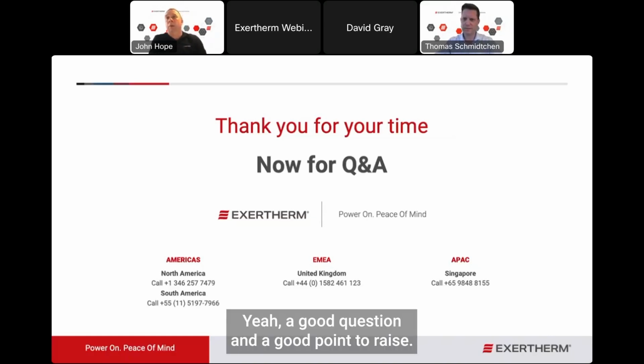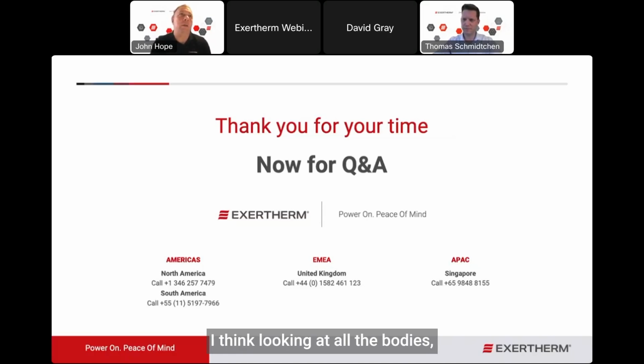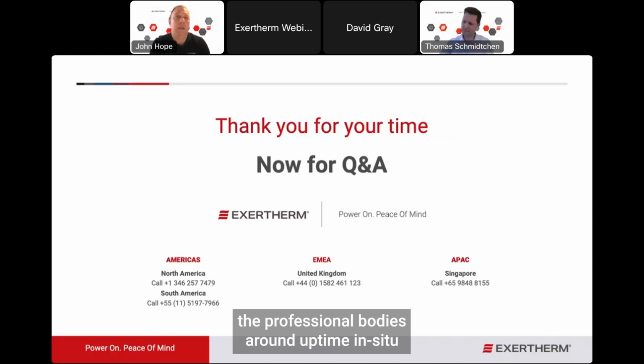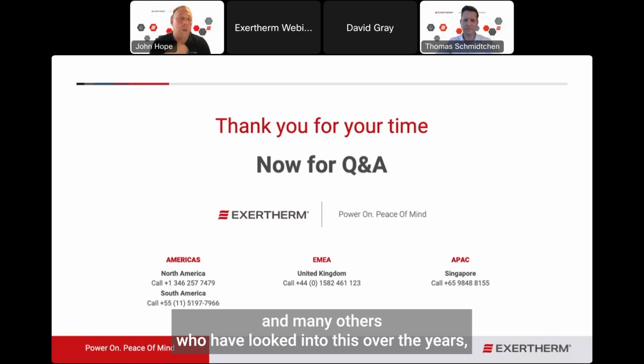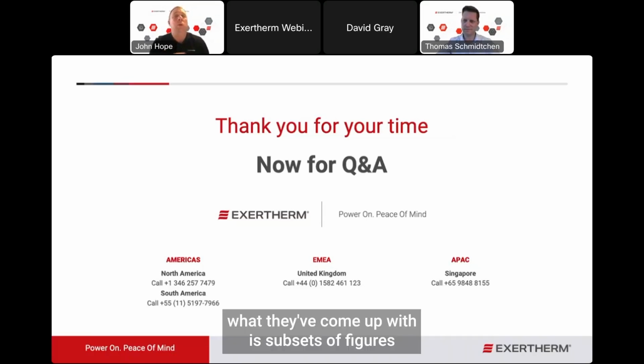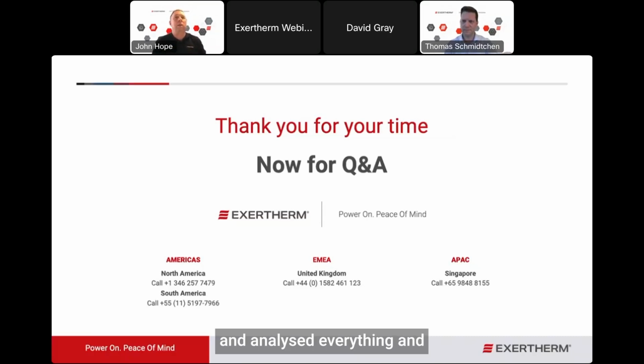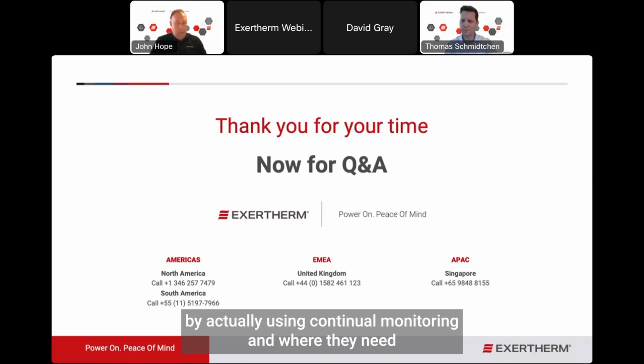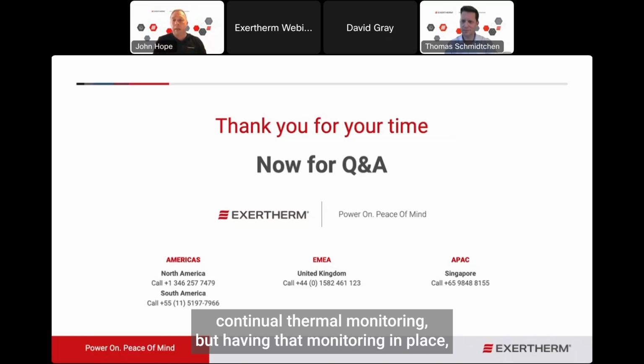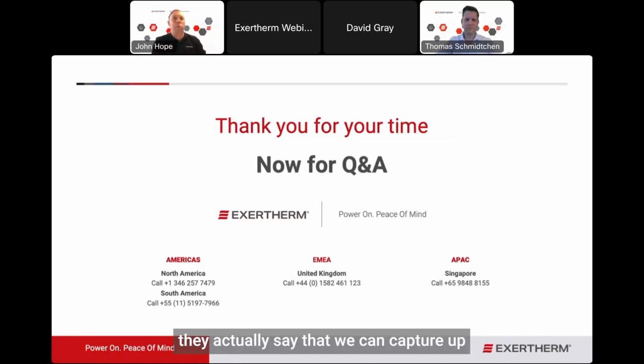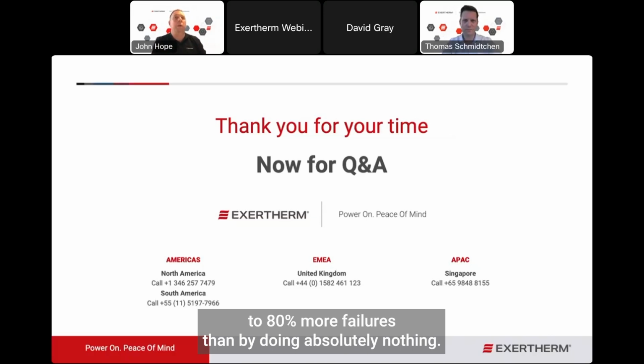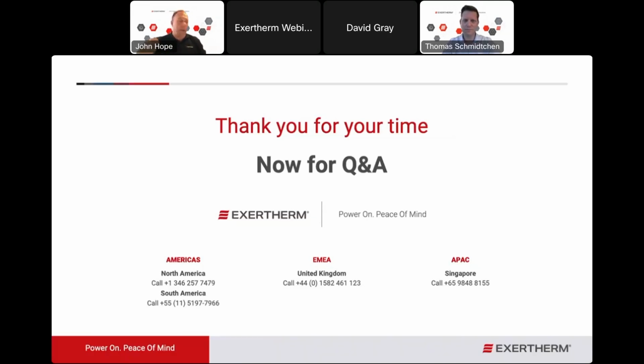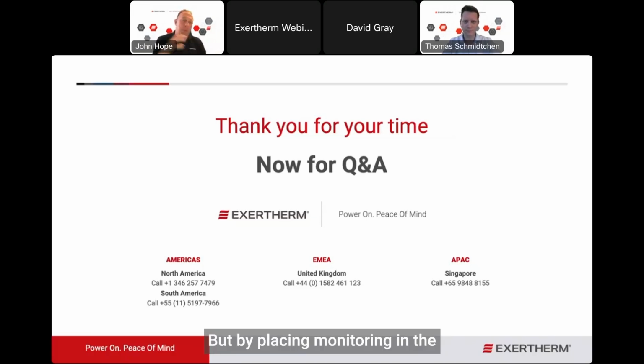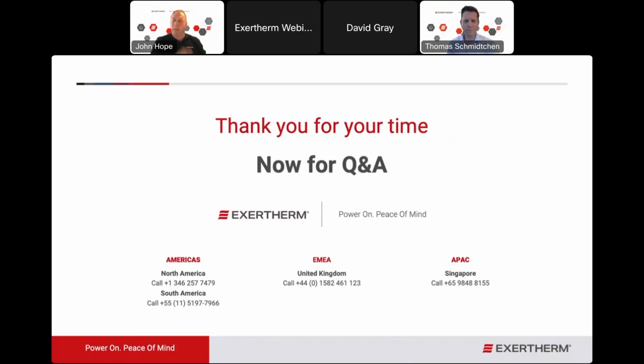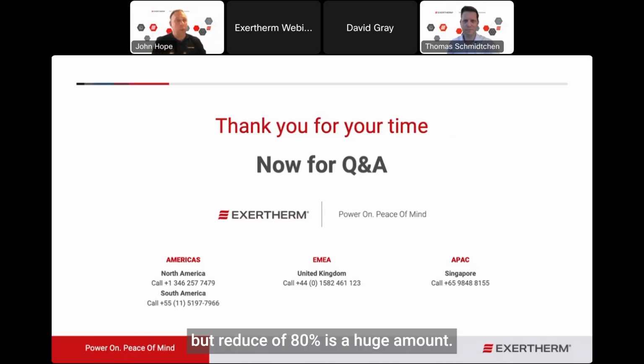Okay. Yeah, actually, a good question and a good point to raise. I think looking at all the professional bodies around, Uptime Institute and many others who've looked into this over the years, they've analysed everything and come up with sets of figures. By using continual monitoring, and we're saying you need continual thermal monitoring, they actually say that we can catch up to 80% more failures than by doing absolutely nothing. So if you have no monitoring in place, you're going to have those 70, 80% plus failures. By placing monitoring in there and knowing the health of your equipment, you're going to catch 80% of those issues. Yes, you're not going to catch all of them, but a reduction of 80% is a huge amount.